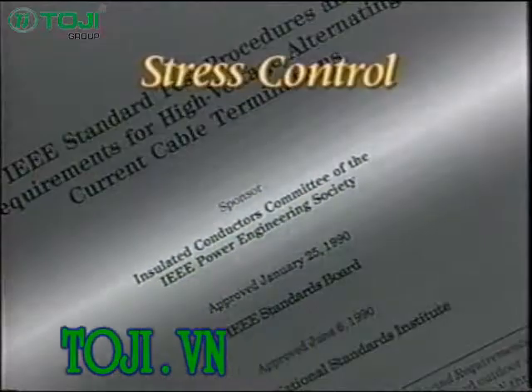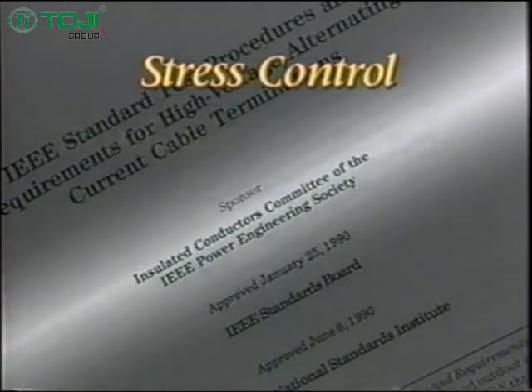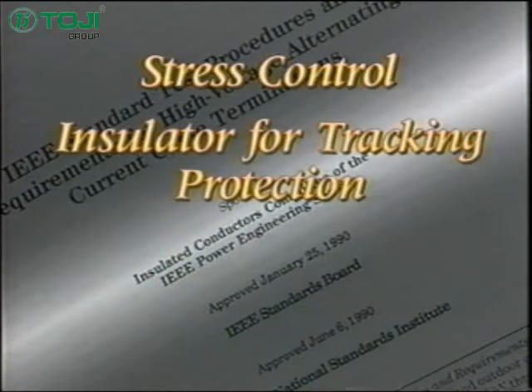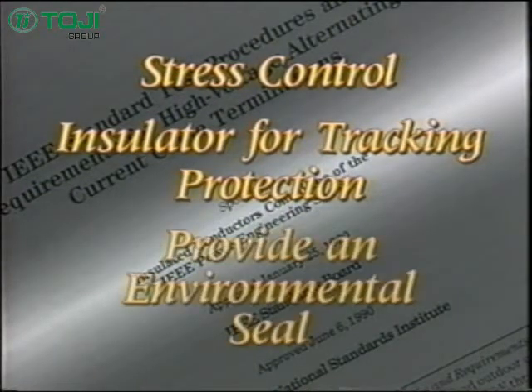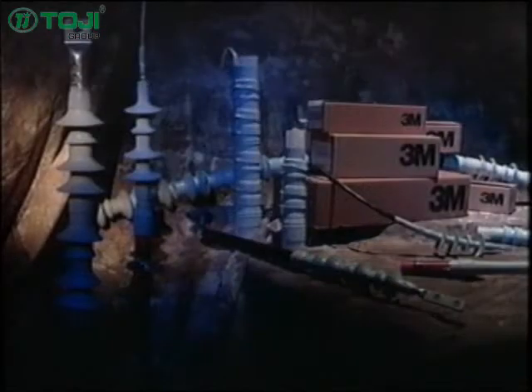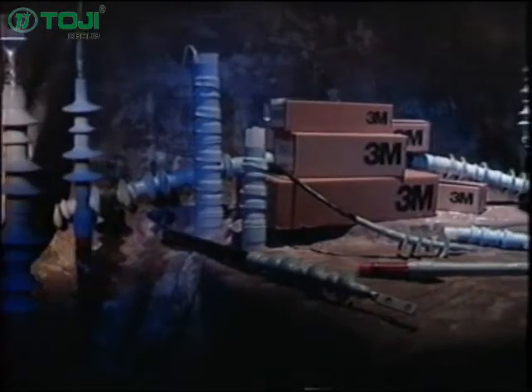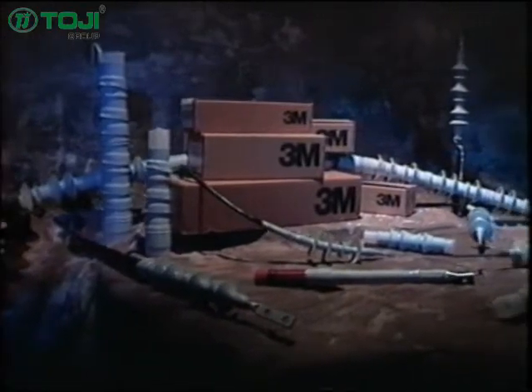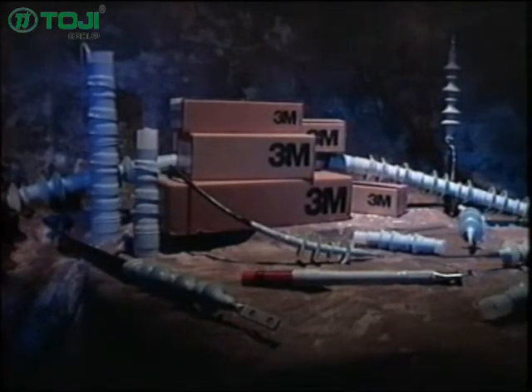First, it must provide stress control. Second, it must provide an insulator for tracking protection. And third, it must provide a seal to the outside environment. 3M provides both a skirted insulator for weather-exposed conditions and a tubular insulator for indoor applications.